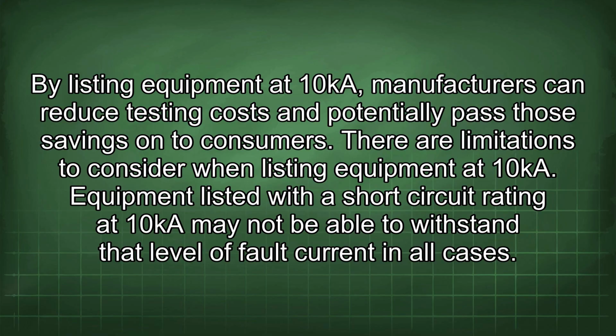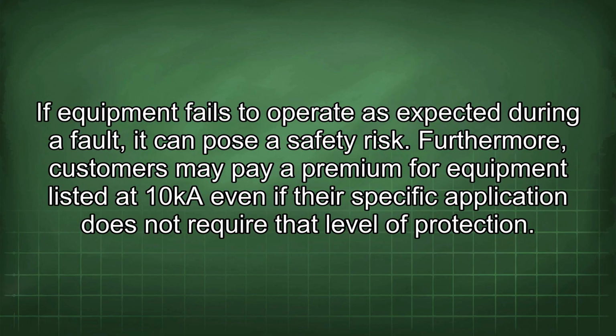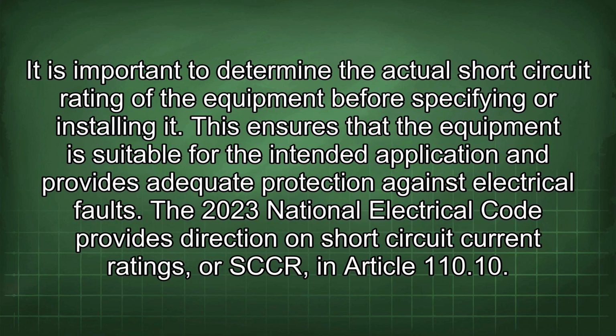There are limitations to consider when listing equipment at 10kA. Equipment listed with a short-circuit rating at 10kA may not be able to withstand that level of fault current in all cases. If equipment fails to operate as expected during a fault, it can pose a safety risk. Furthermore, customers may pay a premium for equipment listed at 10kA even if their specific application does not require that level of protection. It is important to determine the actual short-circuit rating of the equipment before specifying or installing it. This ensures that the equipment is suitable for the intended application and provides adequate protection against electrical faults.